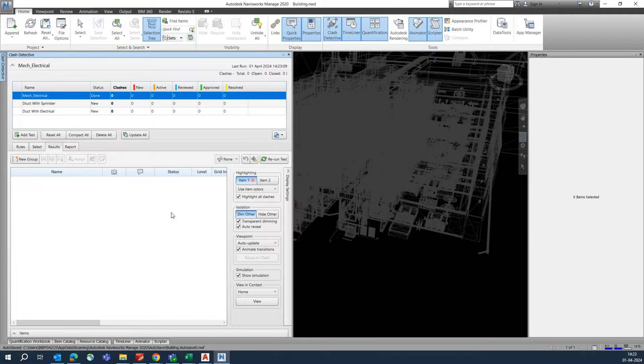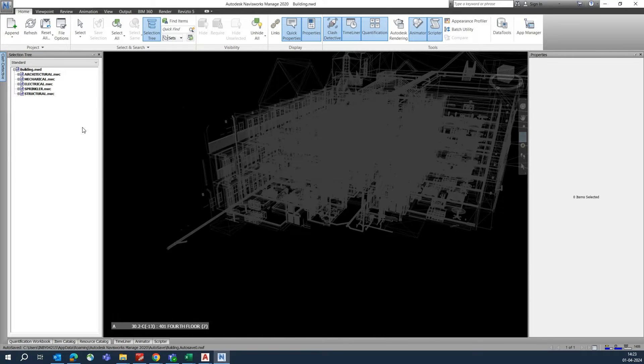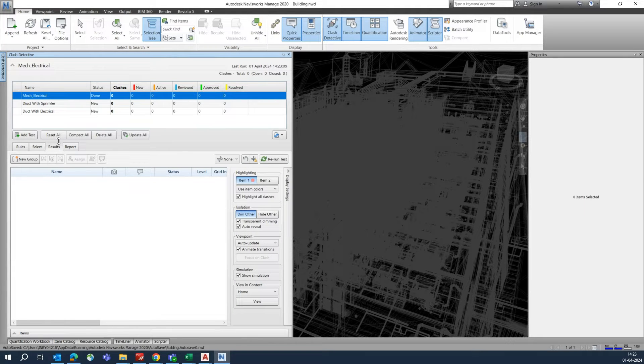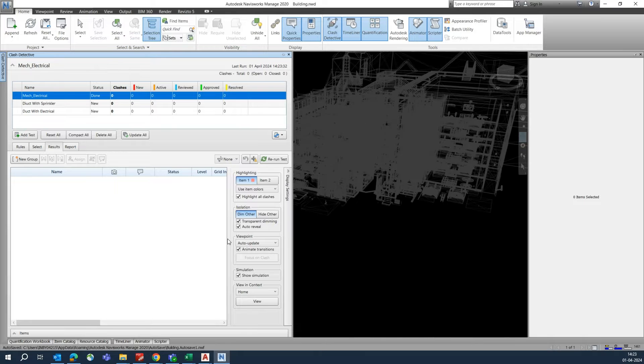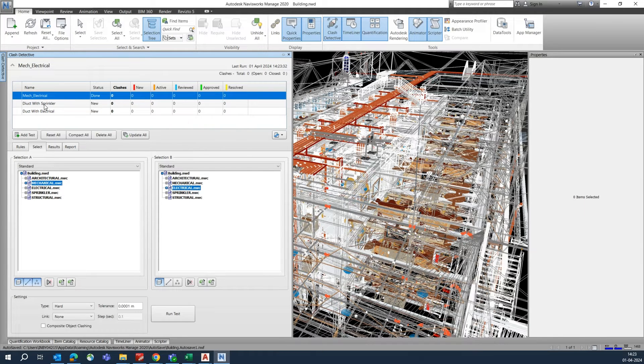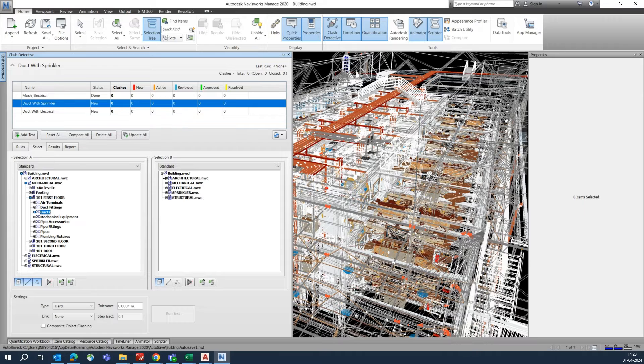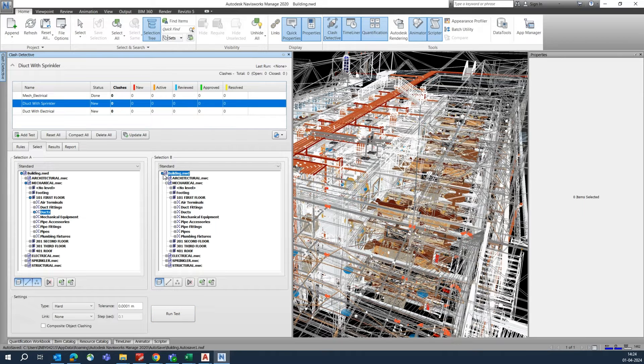The clash results will appear here. If nothing shows up, change the tolerance — for example to 0.01 — and run the test again. Select the mechanical duct for the first floor, then select the sprinkler pipe and fittings. You can also expand under Sprinkler System and choose from there, then run.